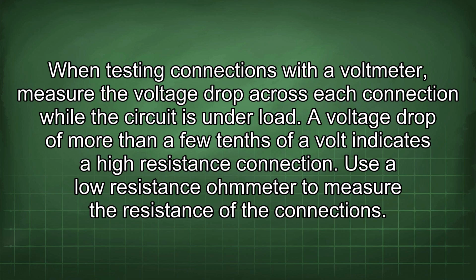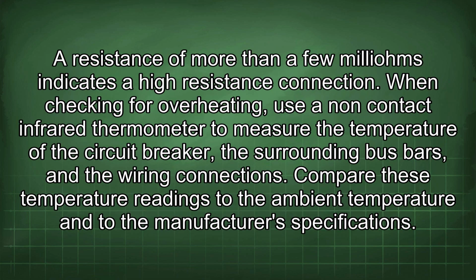When testing connections with a voltmeter, measure the voltage drop across each connection while the circuit is under load. A voltage drop of more than a few tenths of a volt indicates a high resistance connection. Use a low resistance ohmmeter to measure the resistance of the connections. A resistance of more than a few milliohms indicates a high resistance connection. When checking for overheating, use a non-contact infrared thermometer to measure the temperature of the circuit breaker, the surrounding bus bars, and the wiring connections. Compare these temperature readings to the ambient temperature and to the manufacturer's specifications.